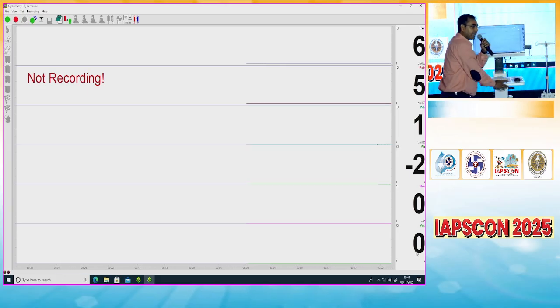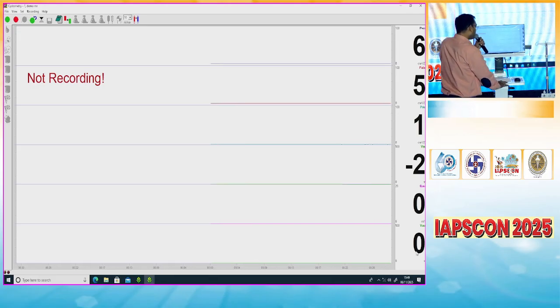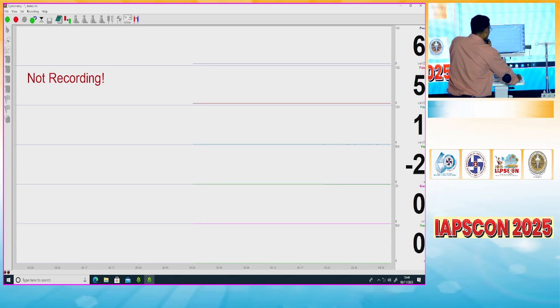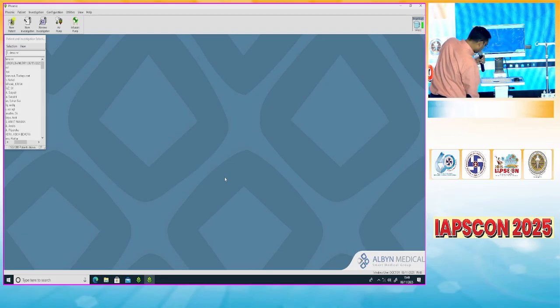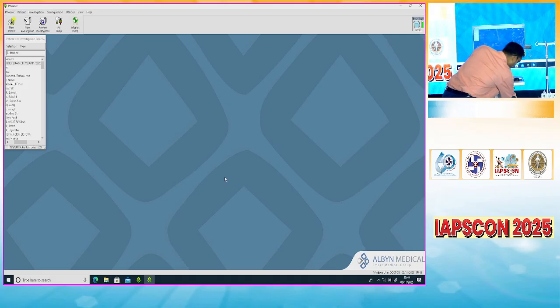You can also add the EMG channel in this protocol. We have already created a protocol which adds the EMG, so now I am showing that. For that we need to take out the EMG from the cradle charger, then only the Bluetooth of the device will activate and connect with the software. So just open it and then click on new investigation again and select cystometry plus EMG. Click OK.